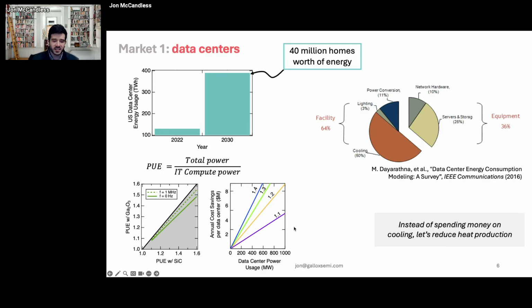In terms of economic savings, this shows data center size in megawatts as a function of PUE. For hyperscalers in the future, at 600 to 1,000 megawatts with a PUE between 1.1 and 1.2, the savings can be in the range of 6 million dollars per year per data center.